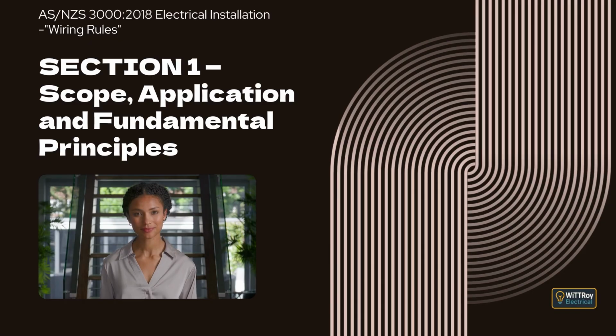Clause 1.6.2 Supply characteristics. When planning or designing an installation, we must know the important details of the electricity supply. We need to know whether the supply is alternating current or direct current. We need to know how many conductors are provided, including phase, neutral, and protective earth for an AC supply. We need to know the voltage and the tolerance. For New Zealand, the nominal low voltage supply is 230 over 400 volts, plus 6% and minus 6%.